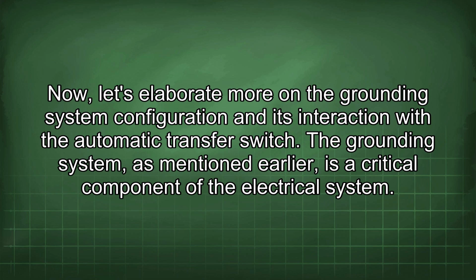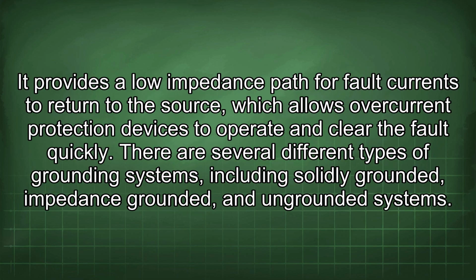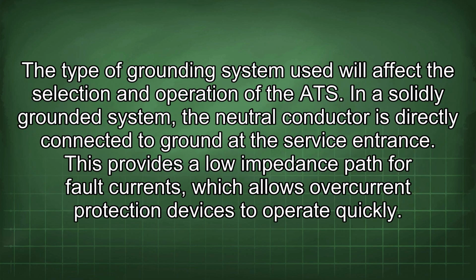The grounding system, as mentioned earlier, is a critical component of the electrical system. It provides a low impedance path for fault currents to return to the source, which allows overcurrent protection devices to operate and clear the fault quickly. There are several different types of grounding systems, including solidly grounded, impedance grounded, and ungrounded systems. The type of grounding system used will affect the selection and operation of the ATS.